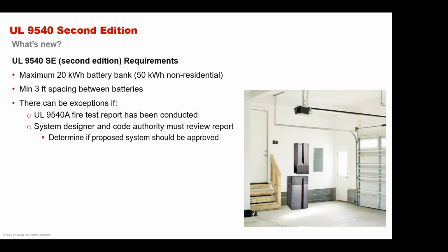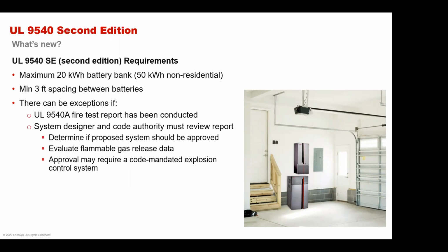Like if the battery manufacturer were to test with a 50 kWh battery system, and they had them adjacent, like 1 foot apart, 1 inch against the wall, and that's how the test was conducted, and there was no propagation of thermal runaway and no explosive gases emitted, then they would probably allow it, but not without that test report. And then they're going to evaluate the flammable gas, and if necessary, the approval to make a bigger system might require a code-mandated explosion control system or some fire suppression system.